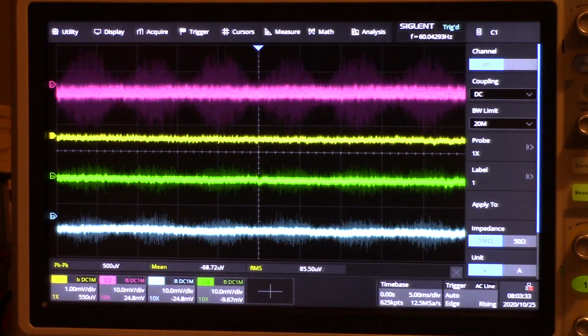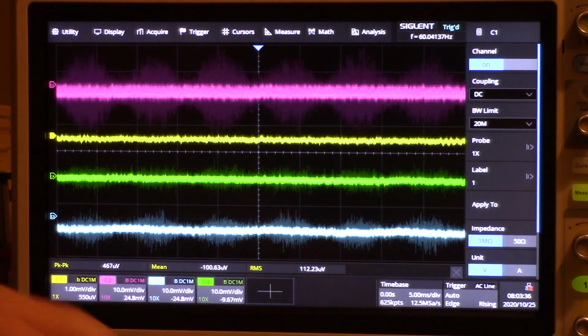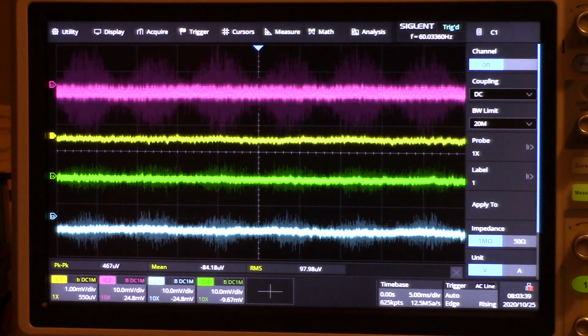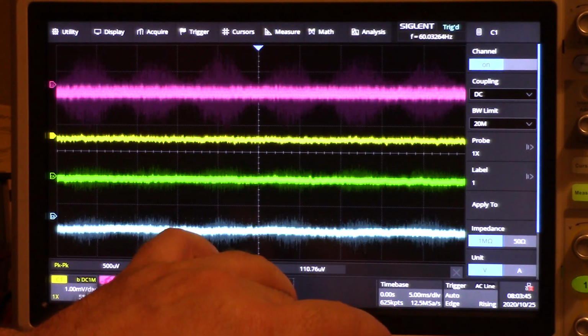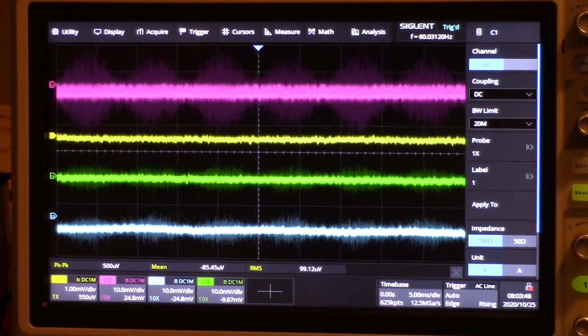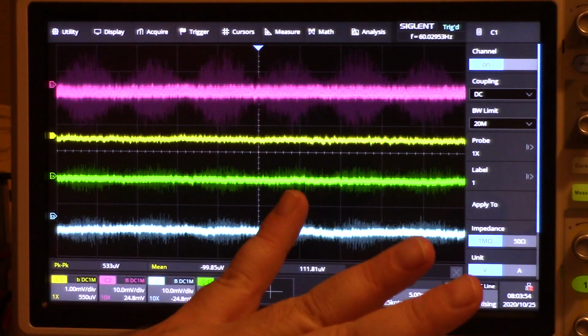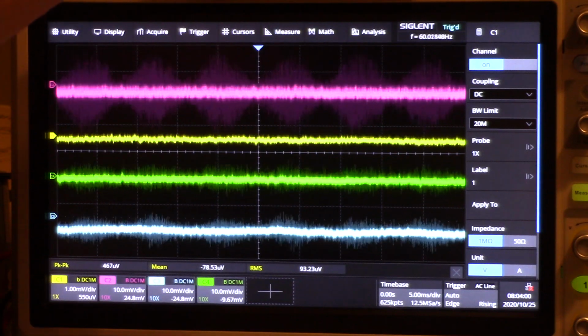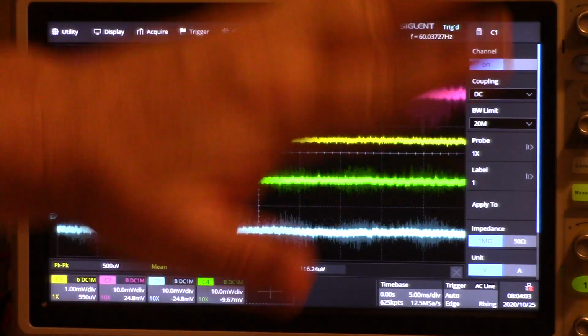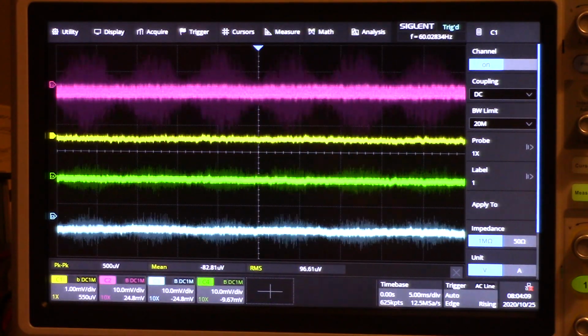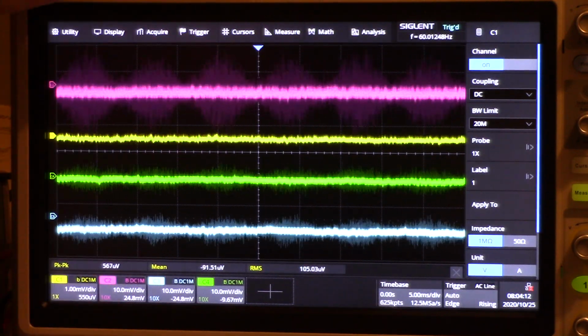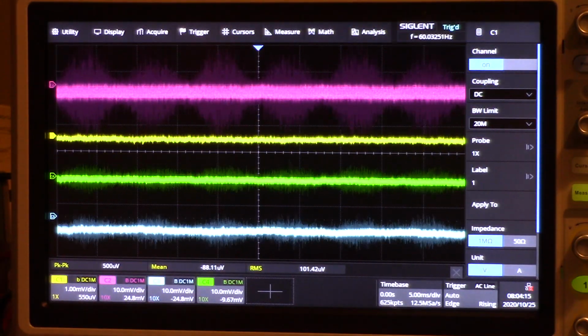So the new probe I purchased, this P6500, is $60. I looked into purchasing four new Tektronix probes and they want $500 apiece. Part of the reason for the cost is that when you have a scope that is 350 megahertz, you have to put 500 megahertz probes on it, because you don't want the bandwidth of the probe interfering with the bandwidth of the scope. So a 350 megahertz scope, you put on 500 megahertz probes, and those are more expensive than the probes you'd buy for a 200 megahertz scope. For a 200 megahertz scope, you'd buy 300 megahertz probes. So that's the issue.